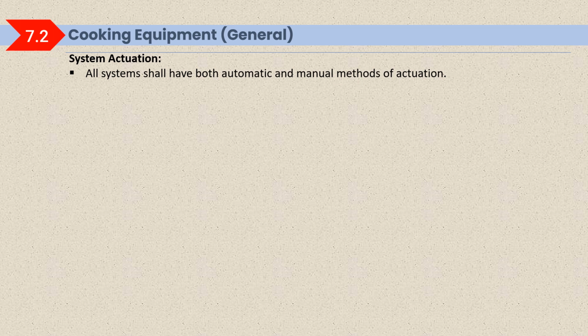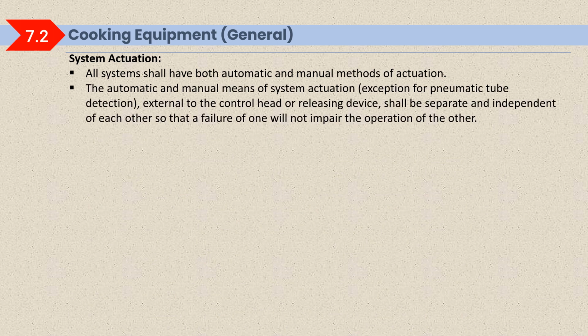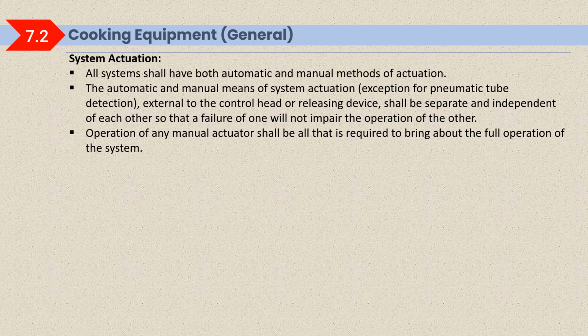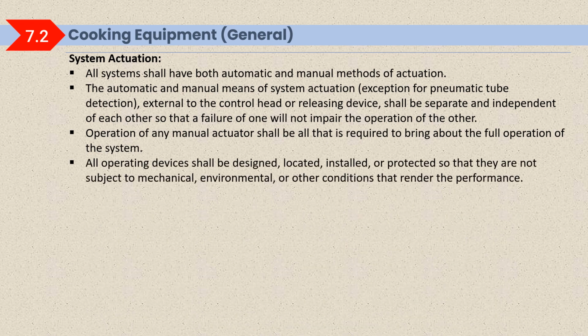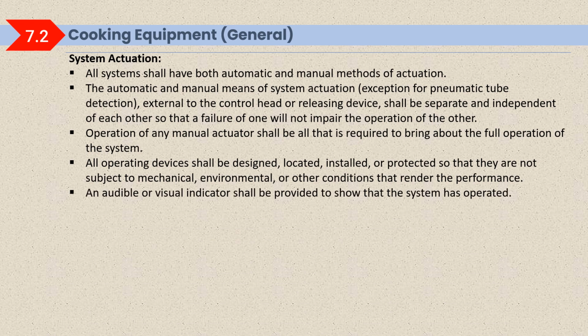System actuation. All systems shall have both automatic and manual methods of actuation. So the fire protection system should have both methods of operation, automatic as well as manual. The automatic and manual means of system actuation, except for pneumatic tube detection, external to the control head or releasing device shall be separate and independent of each other, so that a failure of one will not impair the operation of the other. Operation of any manual actuator shall be all that is required to bring about the full operation of the system. All operating devices shall be designed, located, installed or protected so that they are not subject to mechanical, environmental or other conditions that render them inoperable. An audible or visual indicator shall be provided to show that the system has operated. The extinguishing system shall be connected to the fire alarm system.